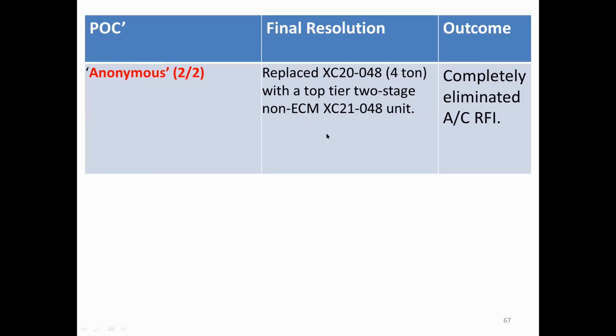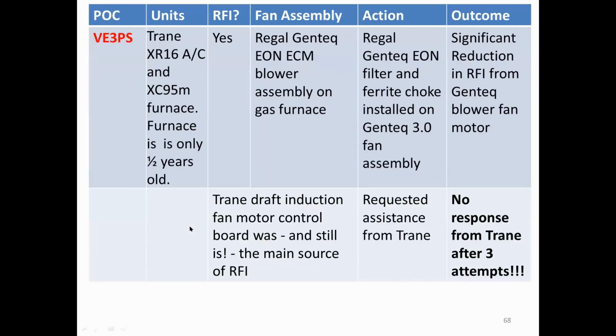And what this gentleman did, again, John Doe, was after substantial discussion with Lennox, they agreed to completely replace his XC 4-ton unit with a top-tier 2-stage unit, which is a 2-stage AC unit. Remember, the compressor has 2 speeds, low and high. It does not have a variable frequency inverter. And this completely eliminated AC RFI. And I can tell you from talking to him, my friend was delighted with this. And here's the last quick example.